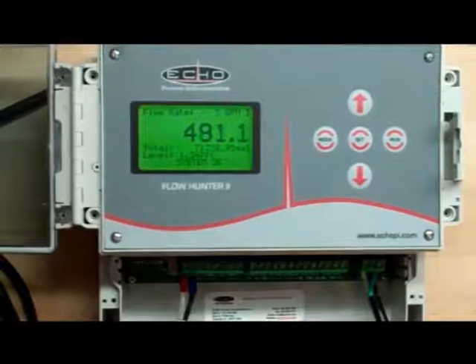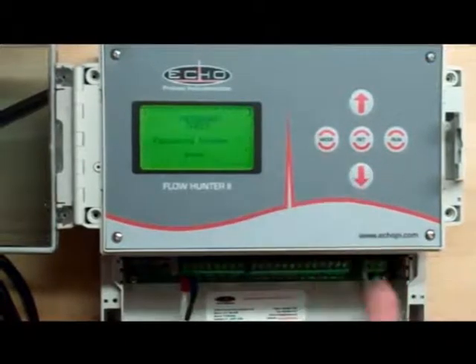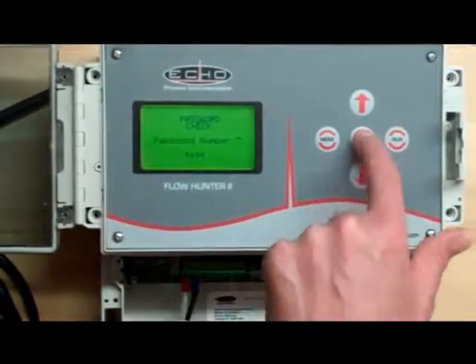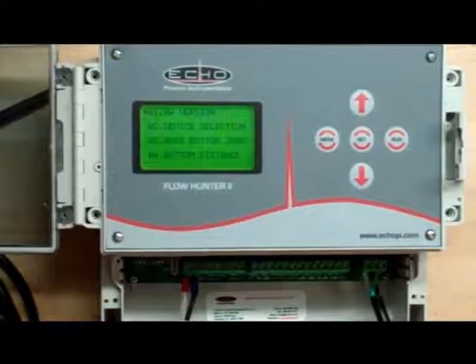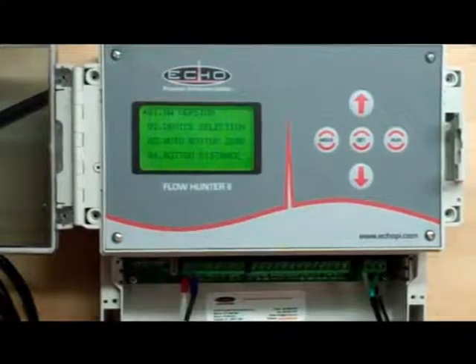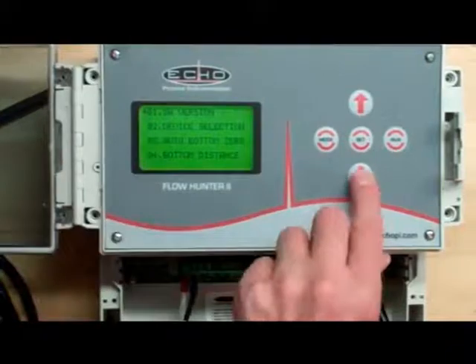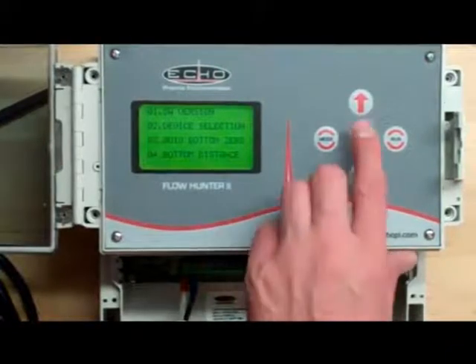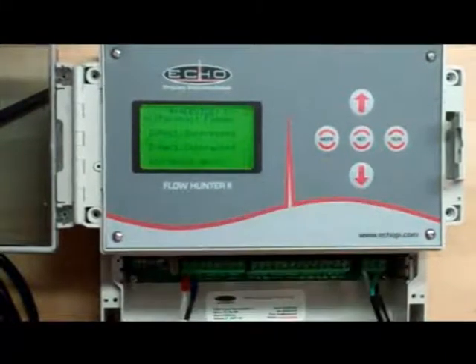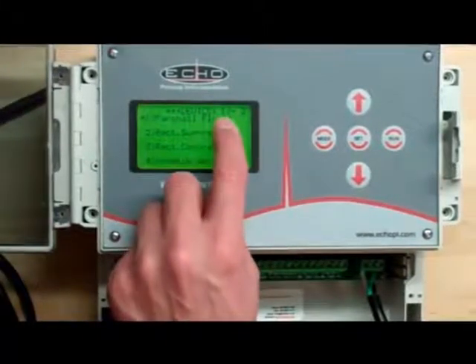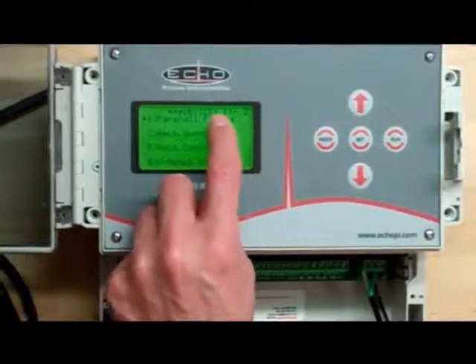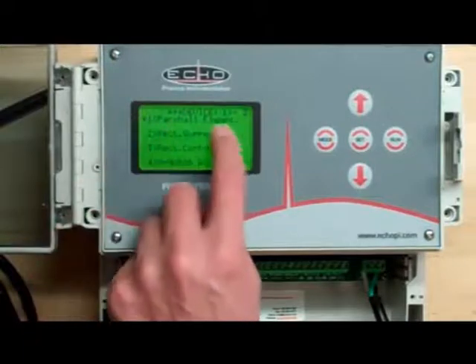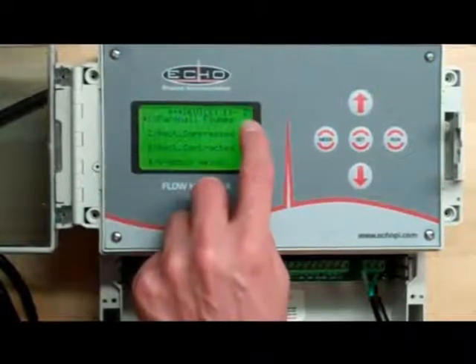It's in run mode. If we hit mode and you see the password come up, hit set, this goes into the menu. First of all, we can go down here to device selection, number 2, hit set. Once we're inside that, if you notice the numbers up here, it says device 1-2. 1 is your device, which is a Parshall flume. 2 is the size of your device.